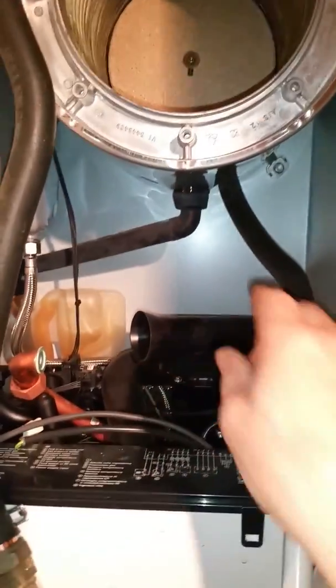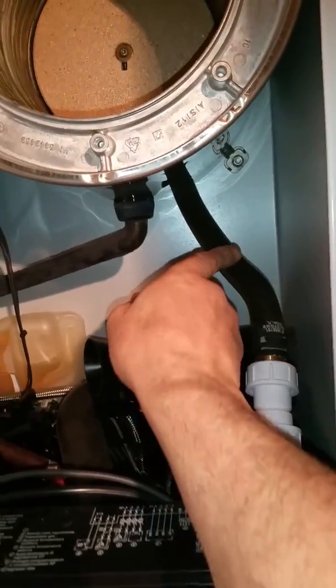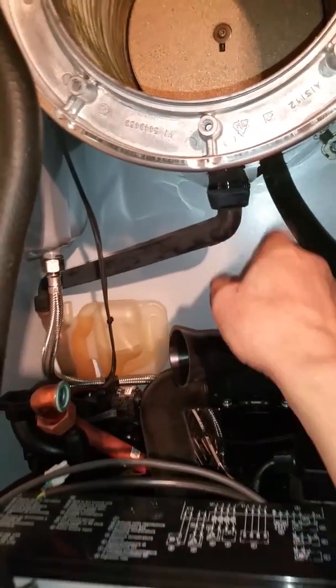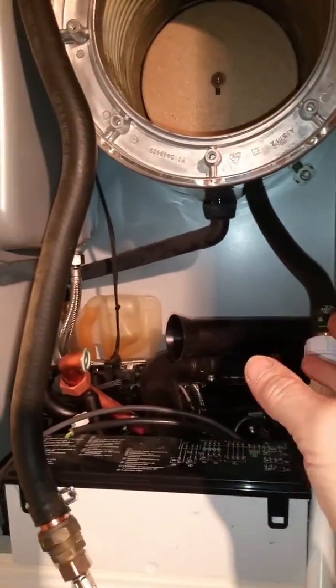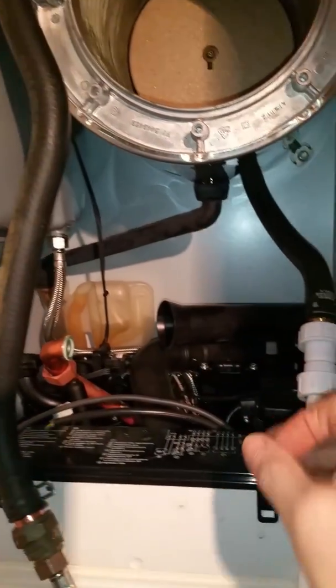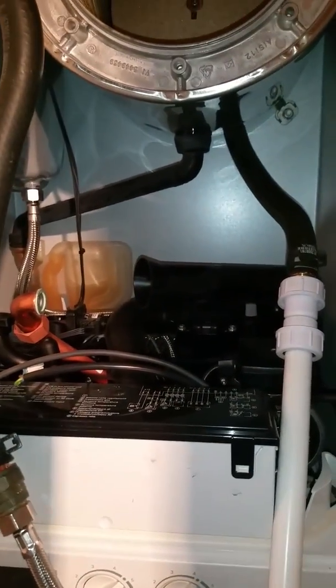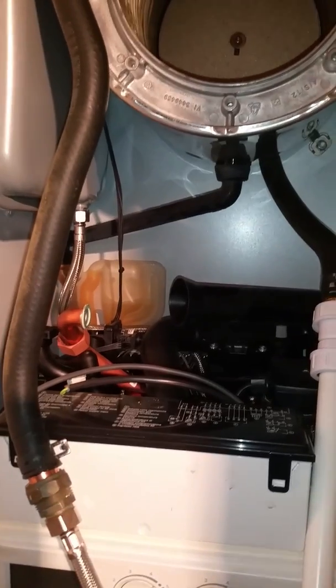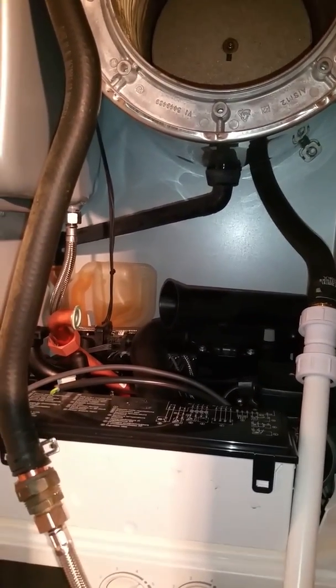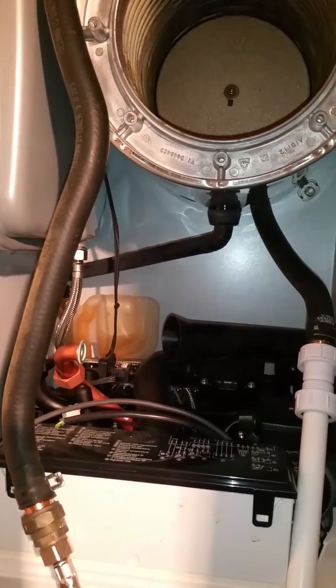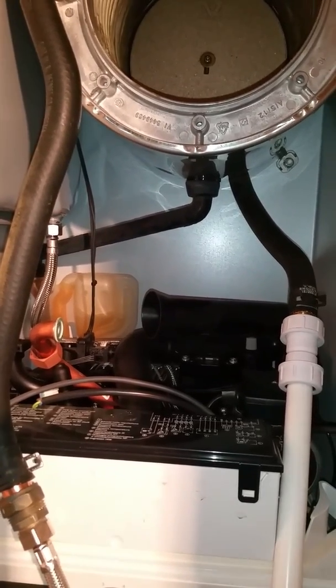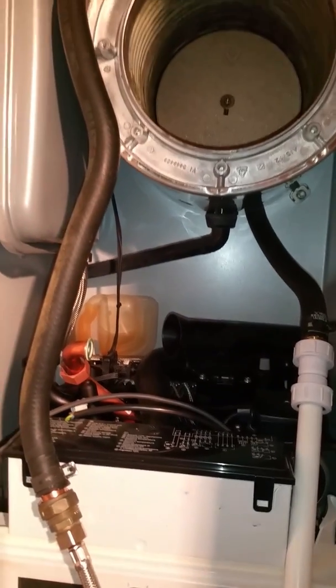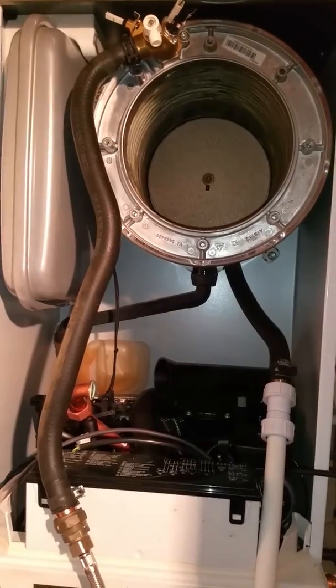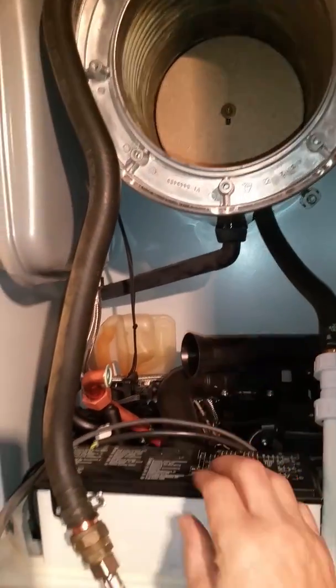So if debris collects in this rear hose, you can no longer just detach it during your service. Normally on the old model, you'd take both hoses out, flush them through, clean out the debris, put them back in, and you've got a really good filtration system to stop dirt collecting in the boiler generally. I know some people don't agree with me on that, but it's worked very well for me over time.